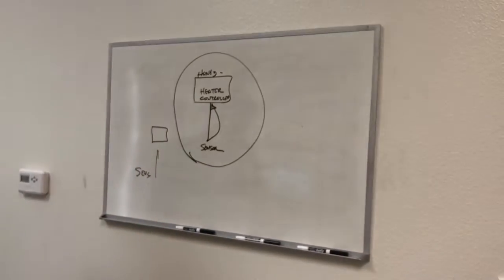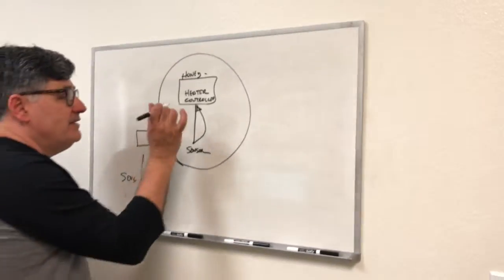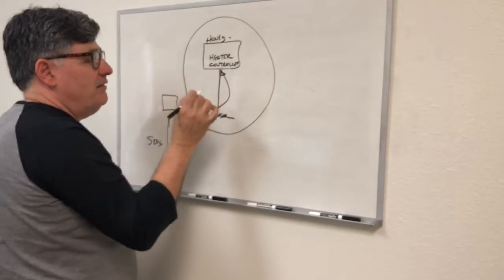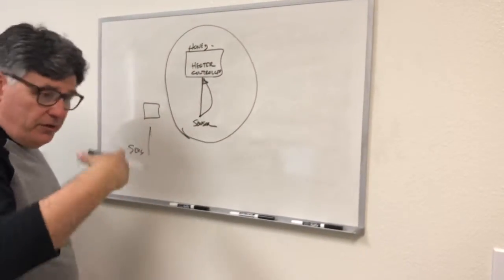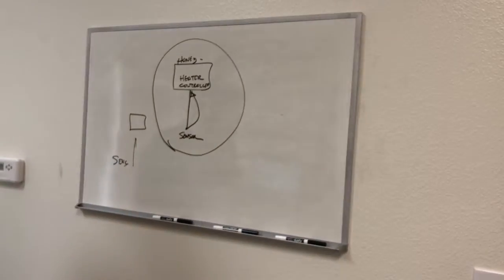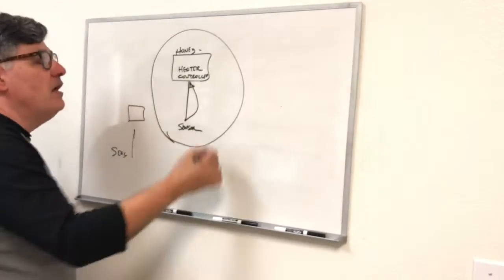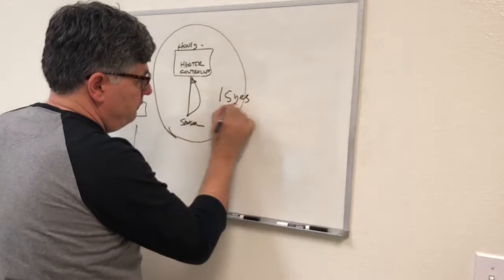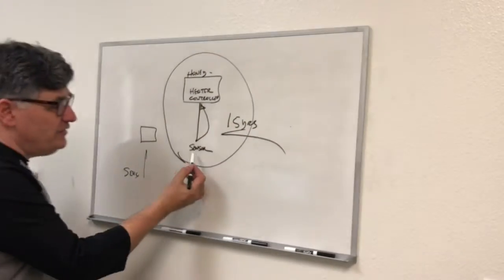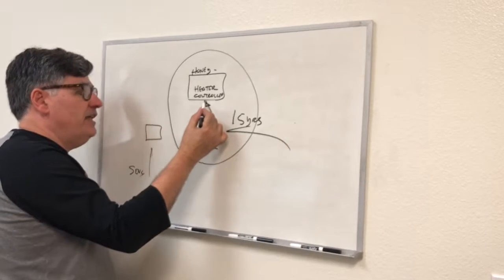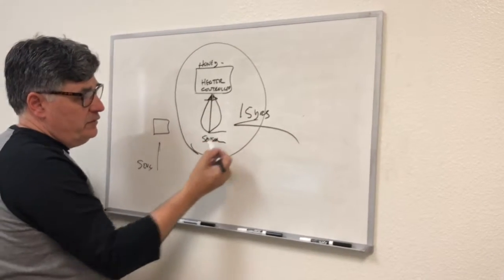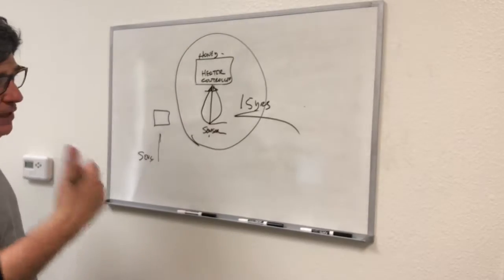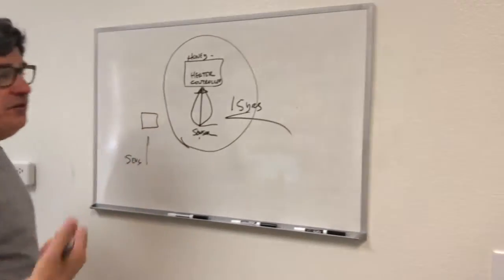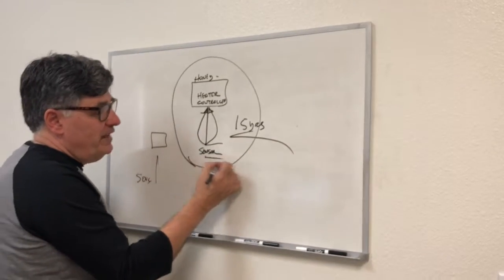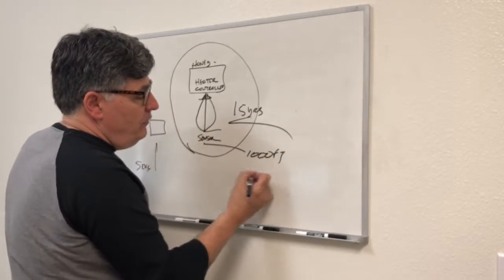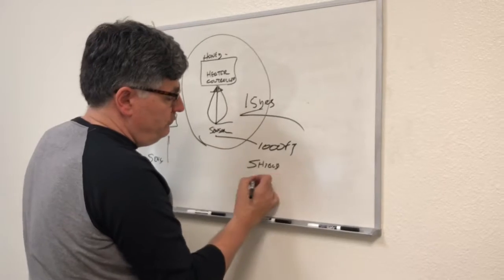Yes, we don't have the fancy touch panel controls and all that good stuff, but we've got the Honeywell T775 controller, the ones you bought and are having shipped to me. Those are bulletproof because I've been using them inside control panels with VFDs for over 15 years with no interference issues, because they've got a sensor 100% matched to the heater controller, using what's called a thermistor. It's a totally different type - not a thermocouple, not an RTD. It's a thermistor, and you can run the sensor out 1,000 feet without shielding or grounding cables.